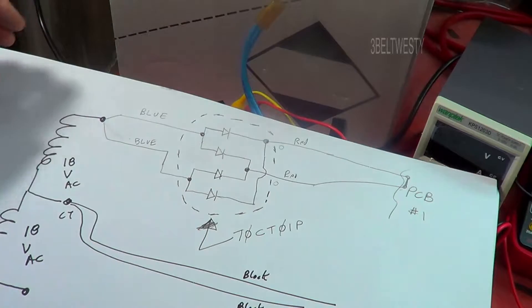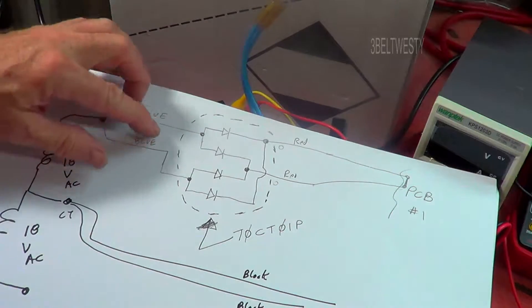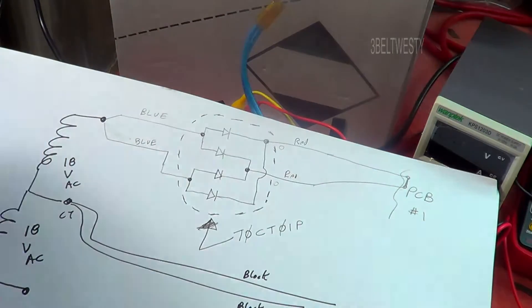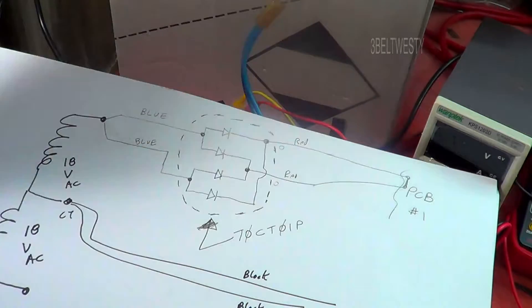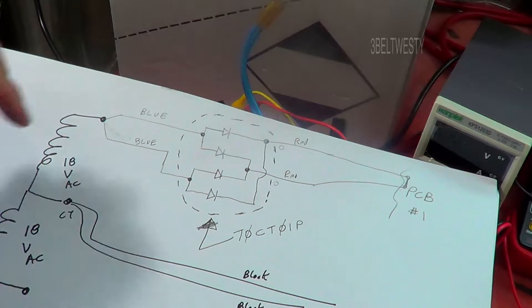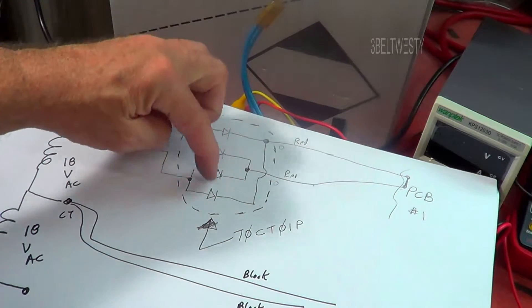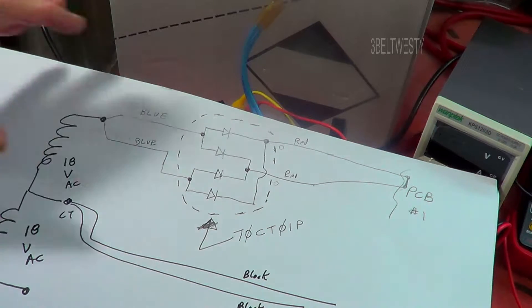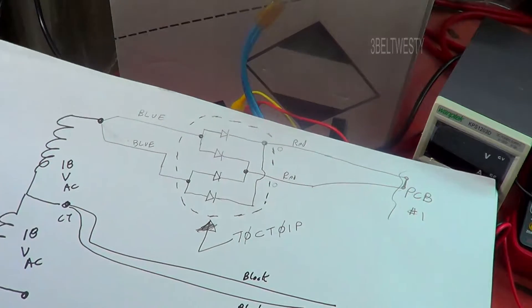But the way this is used is they're feeding it such that the two blues are going. It's hooked up electrically as though it's one big diode. So if this was running and you went in there magically and could zap either one of these diodes, they're all basically working. That's how they get the current capability up on the device. Now there's a sister module down over here too.